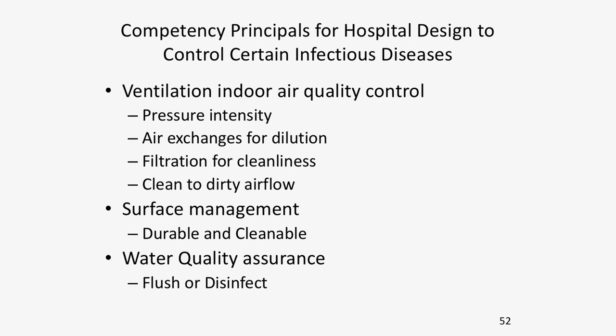Competencies for principal - competency principles for hospital design to control certain infectious disease. We really want ventilation, and that's the pressure intensity - those are spec'd out. Air exchanges for dilution, filtration for cleanliness of that air, and then clean-to-dirty airflow. We need to know that. Those are principles and competencies that all construction workers should understand, even though they read a print quite differently than the way that you and I would read a blueprint.